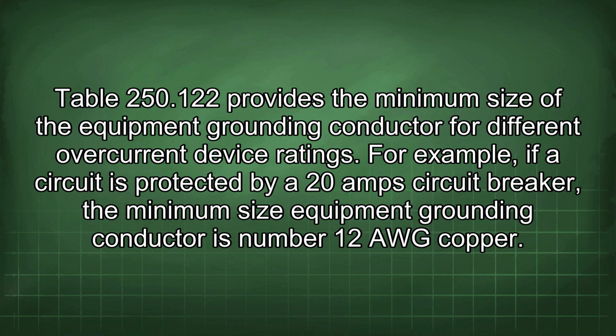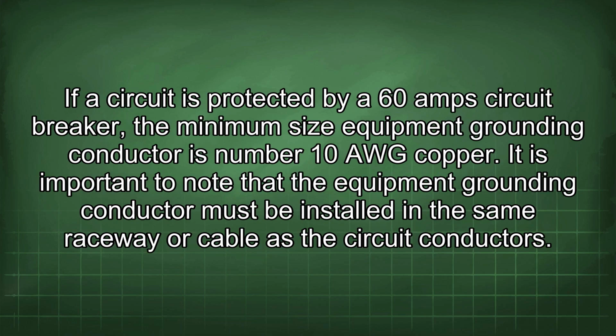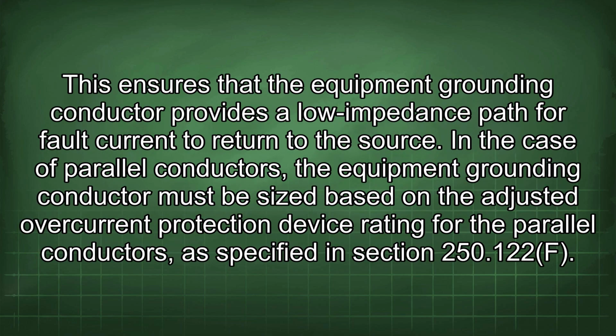For example, if a circuit is protected by a 20 amp circuit breaker, the minimum size equipment grounding conductor is number 12 AWG copper. If a circuit is protected by a 60 amp circuit breaker, the minimum size equipment grounding conductor is number 10 AWG copper. It is important to note that the equipment grounding conductor must be installed in the same raceway or cable as the circuit conductors. This ensures that the equipment grounding conductor provides a low impedance path for fault current to return to the source.